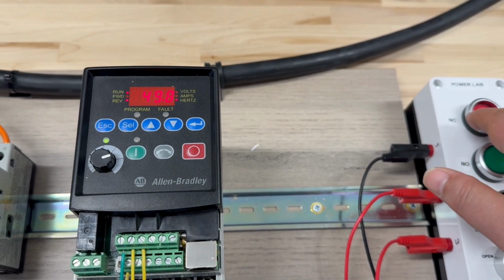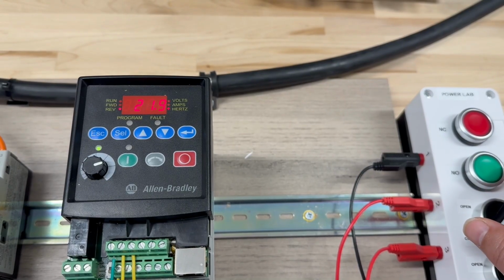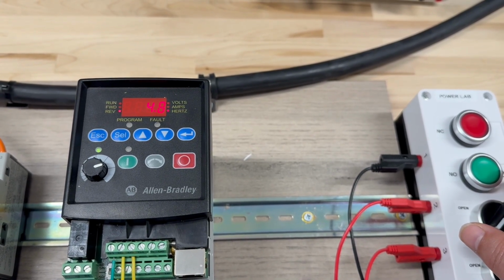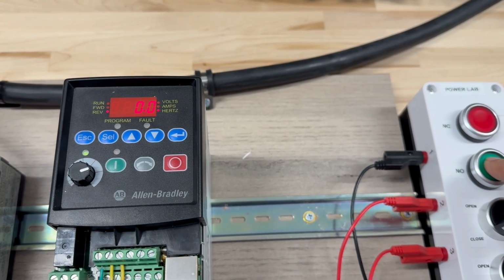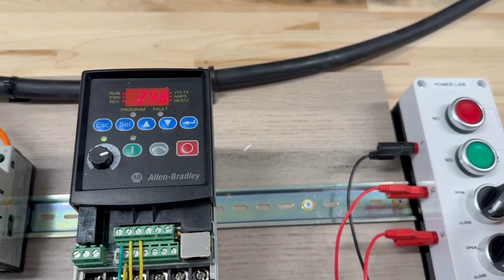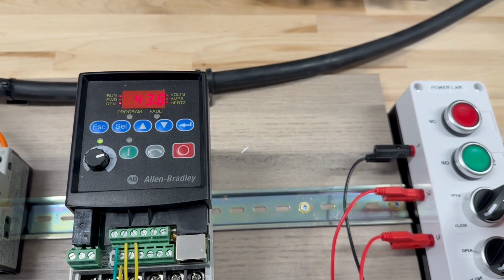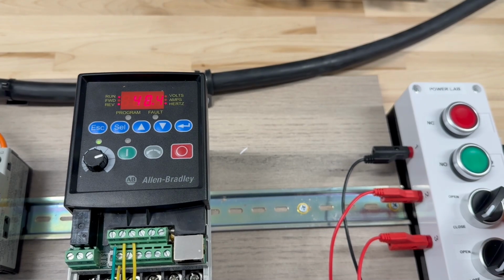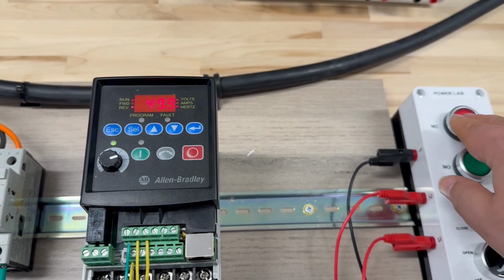Same thing for deceleration. Now the rate is slow, now it's going very fast, and again close to 0 it should be much slower, right? Let's check that again. Again it's slower in the beginning, then the change rate goes up and gets faster, and again close to the max frequency it should slow down, which follows the S curve that happens in 20 seconds for our case.